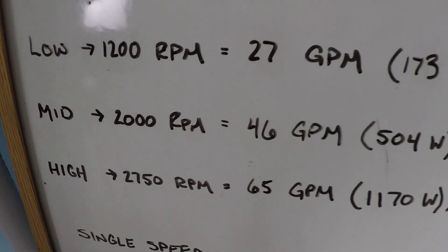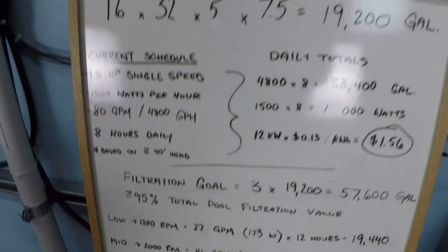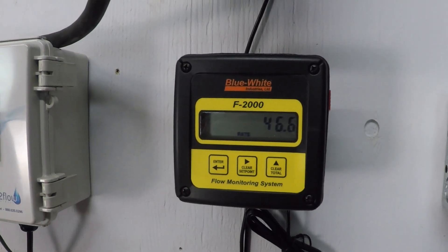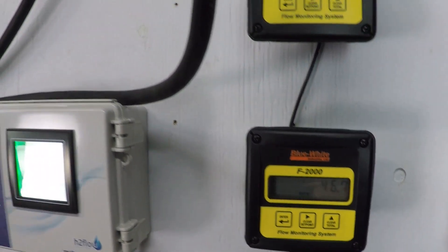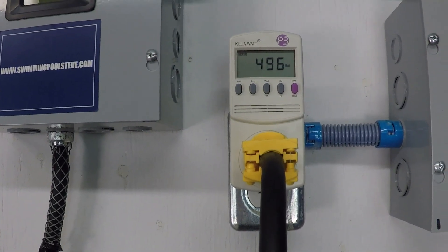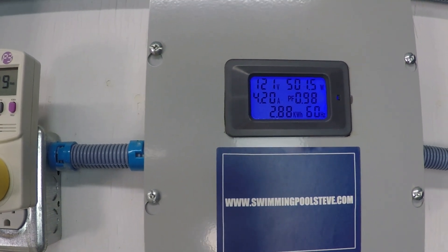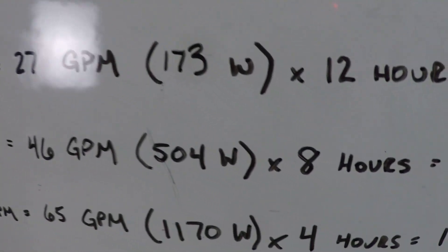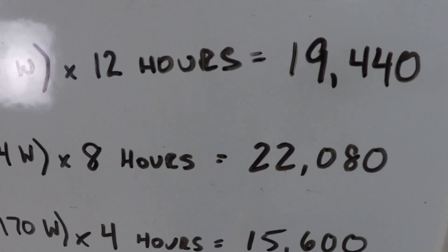Here we're looking at 2000 RPM, and we're expecting to see about 500 watts and about 46 gallons per minute, which is what this system is able to achieve. Just over 46, almost 47, just over 500 watts. Over the course of 8 hours, we're achieving 22,080 gallons.